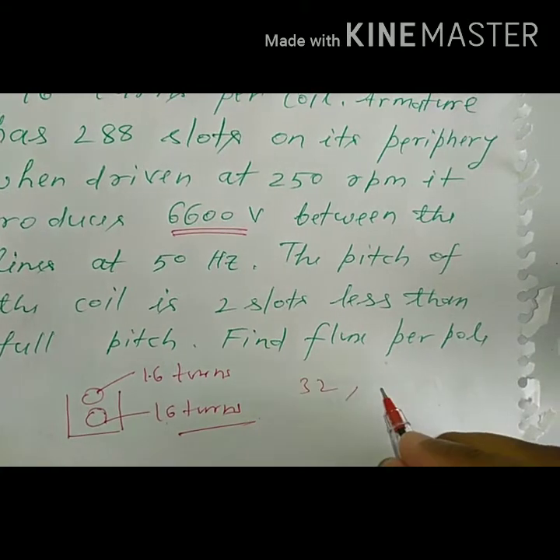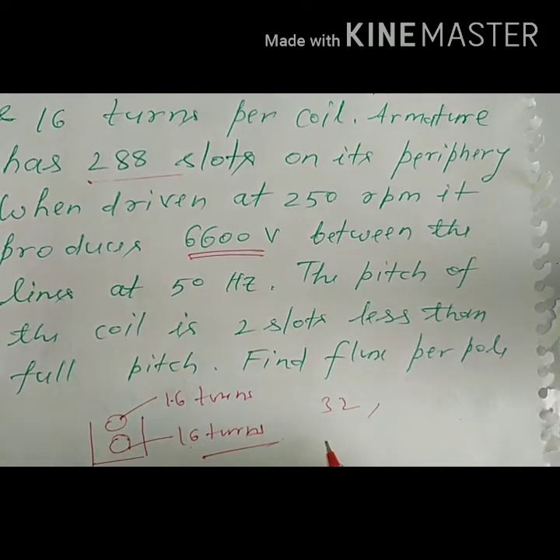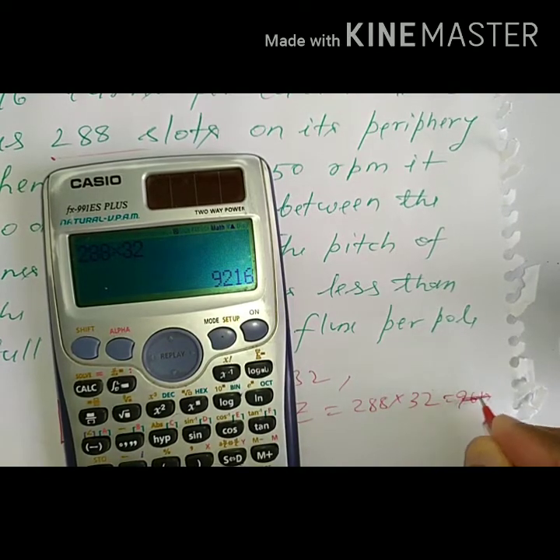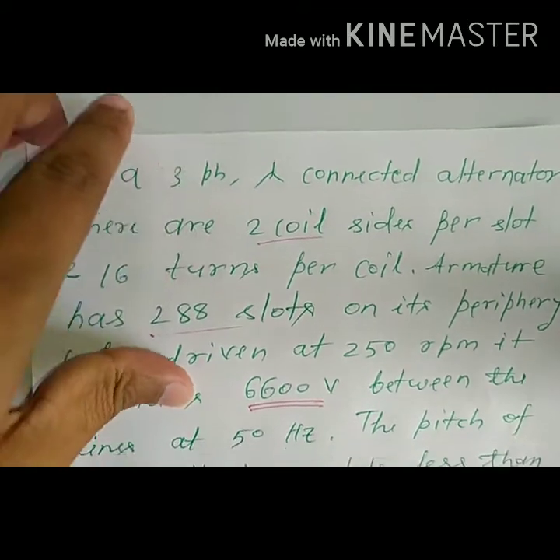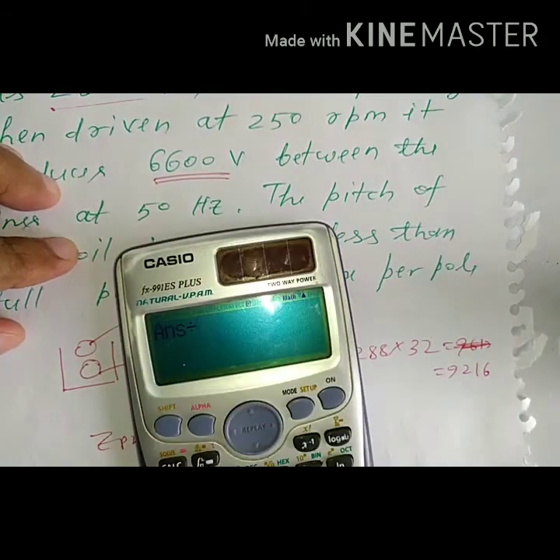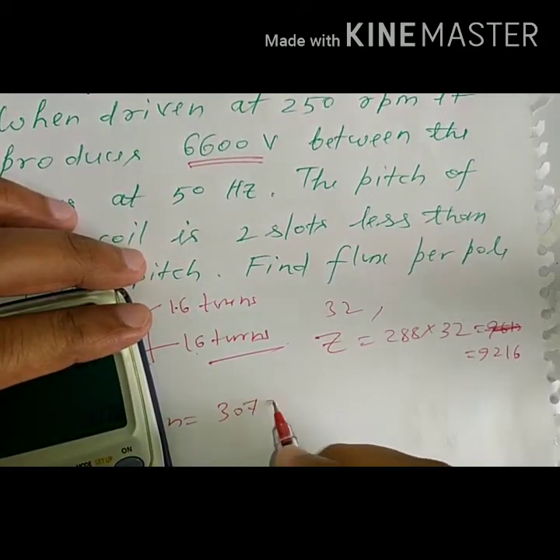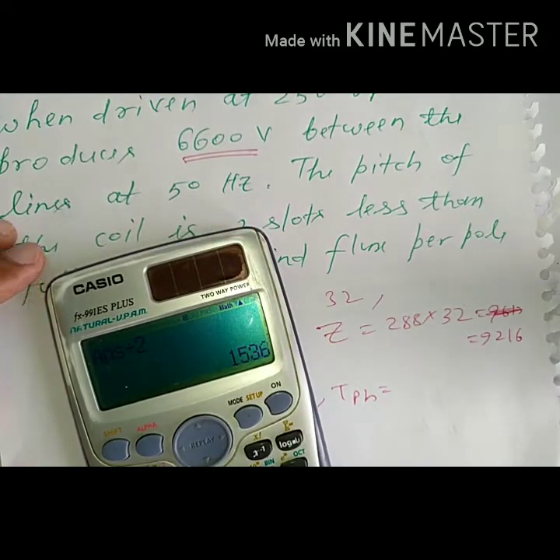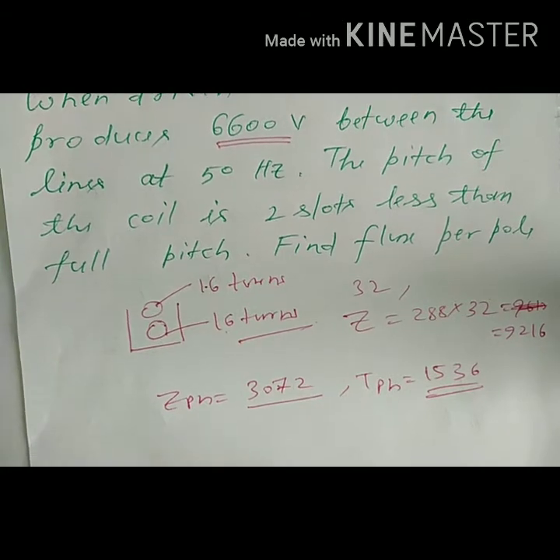Each slot has 32 conductors and there are 288 slots. So total Z equals 32 into 288 = 9216. Since this is a three-phase machine, conductors per phase Z_ph = 9216 divided by 3 = 3072. Therefore turns per phase T_ph = 3072 divided by 2 = 1536.